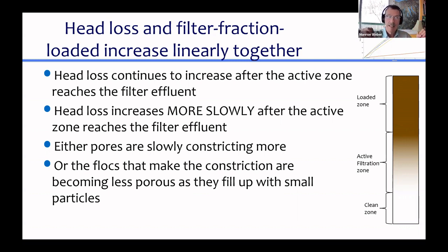So maybe it takes, let's say, a minute for one of those pores to fill up. Then in 2 minutes, 2 of those pores are filled up, and in 3 minutes, 3 of those pores are filled up. And as you're coming down through the filter, by the time you get to 5 minutes, you've got to go through 5 of those clogged pores, and you've got the head loss of 5 of those pores to deal with. Did that make sense? So head loss increases linearly with time because the number of formed and fully constricted pores is increasing linearly with time.